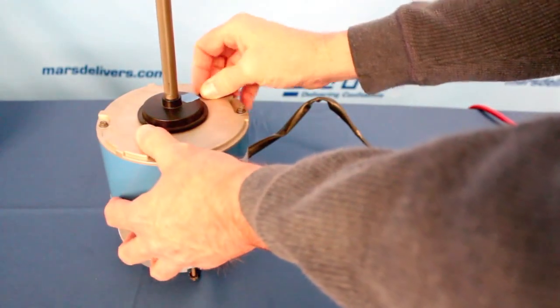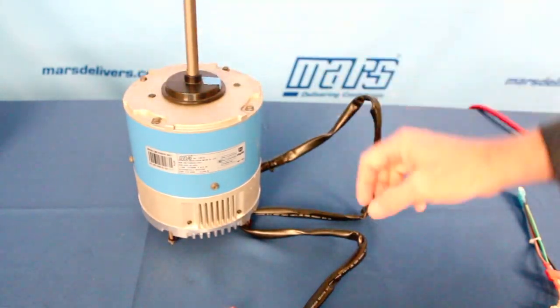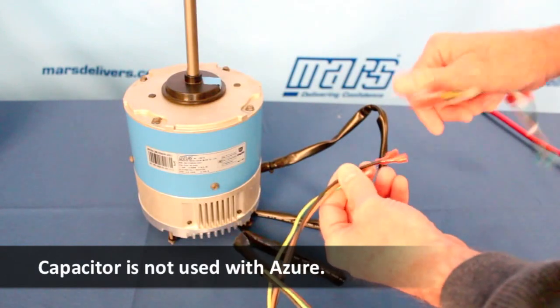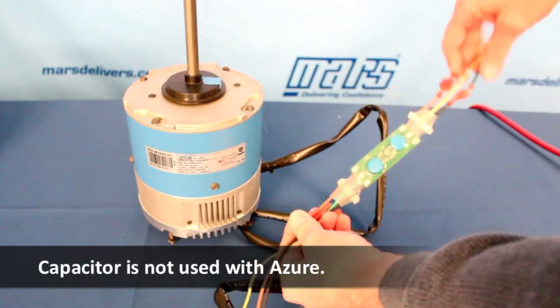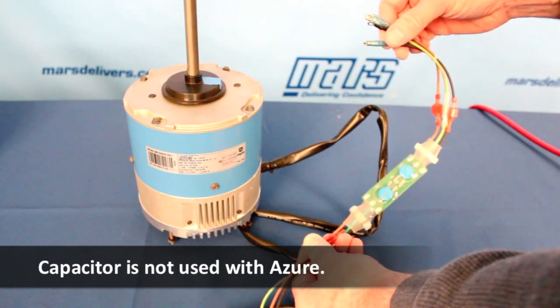There are rubber plugs on here. So if you mount the motor shaft down, you want to remove these two rubber plugs on this plate here. Run the harness through the conduit of the condensing unit and into the control box. Then you will attach the surge protector and make the connections to ground and to the contactor. And that's all there is to it.